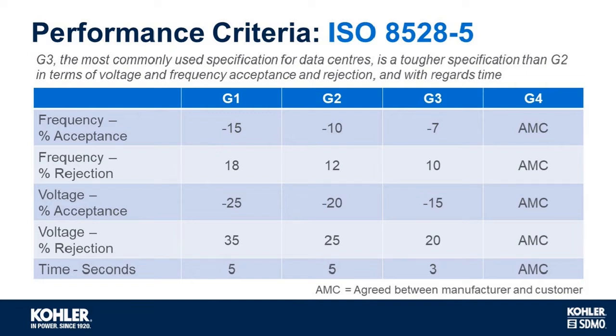Okay, so let's look at the governor classification as set out in ISO 8528, which is the international standard that stipulates how a generator should perform when it's loaded. G3 is the most commonly used governor classification for data centres, as it's a tougher specification than G2. So as you can see, the G3 criteria has a frequency acceptance of minus 7%, a frequency rejection of plus 10%, a voltage acceptance of minus 15%, a voltage rejection of plus 20%, and a recovery time to steady state within 3 seconds. This criteria sets the benchmark for generator performance and should allow engineers to compare one manufacturer to another.